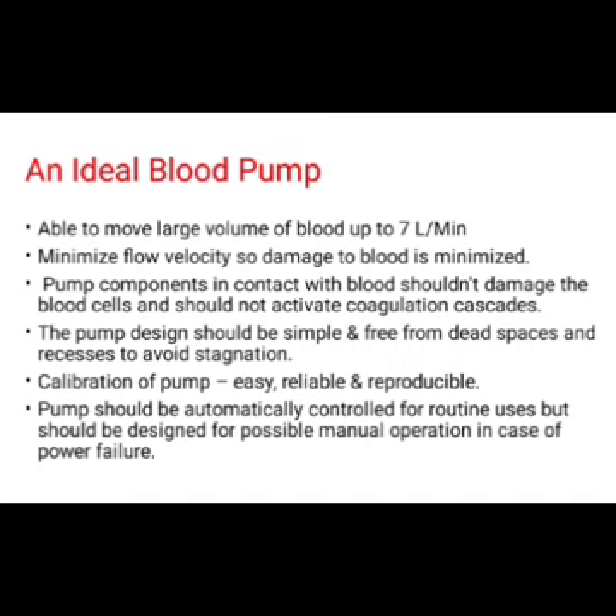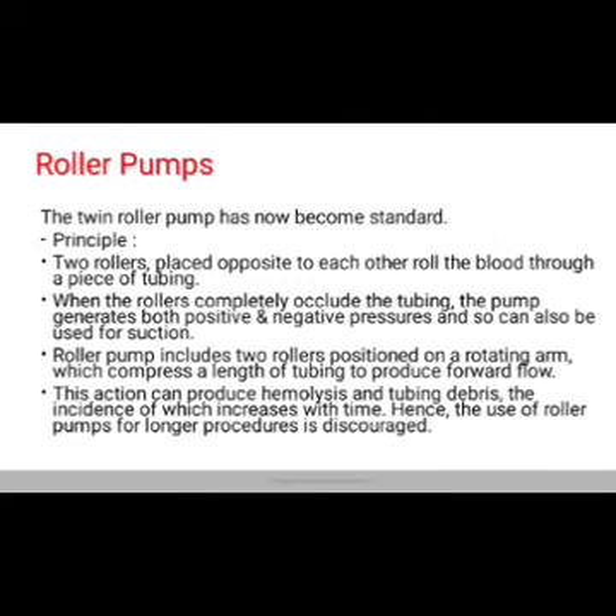The design should be simple and free from dead spaces and recesses to avoid stagnation. Calibration of the pump should be easy, reliable and reproducible. The pump should be automatically controlled for routine use but should be designed for possible manual operation in case of power failure. The roller pumps. The twin roller pump has now become standard.